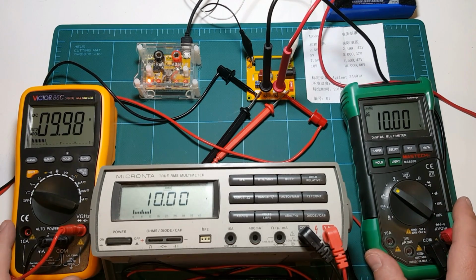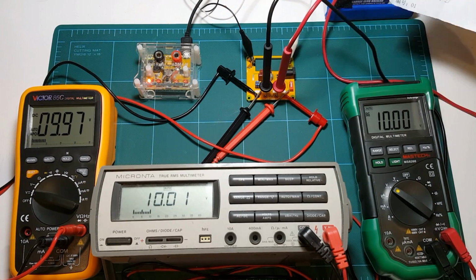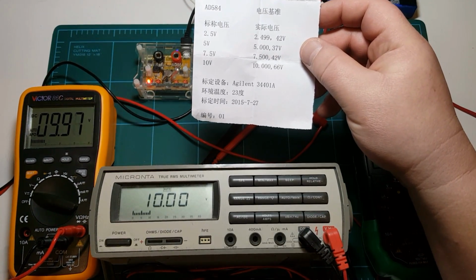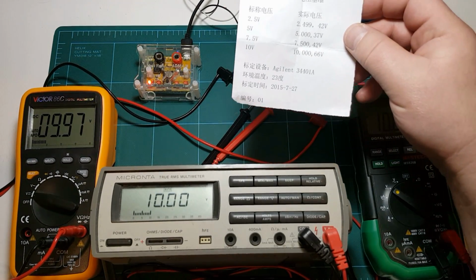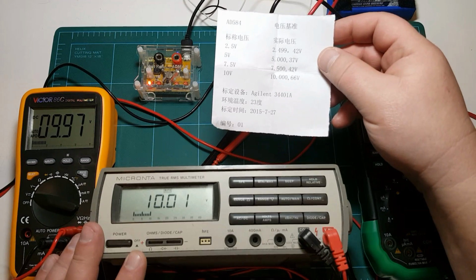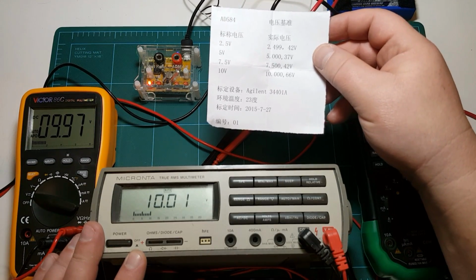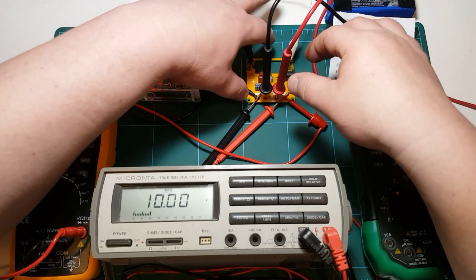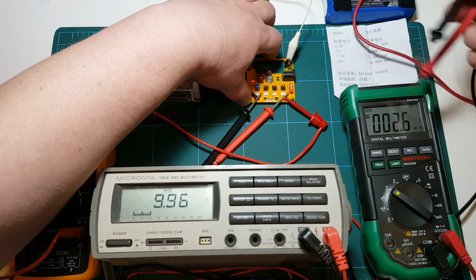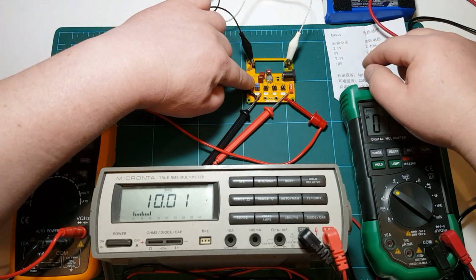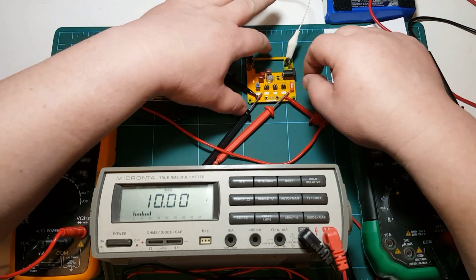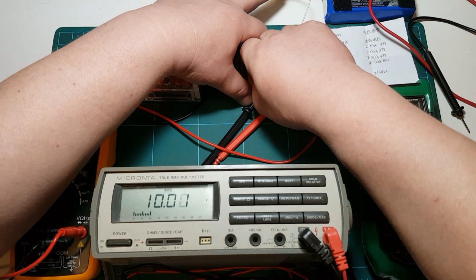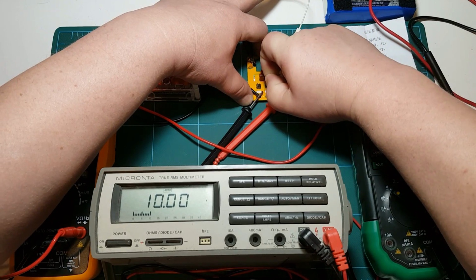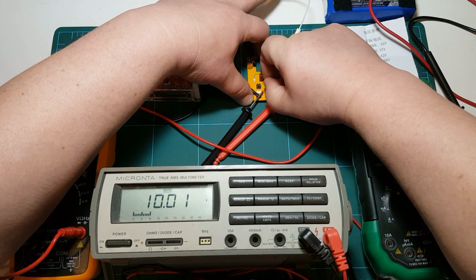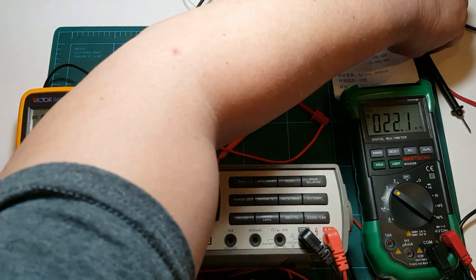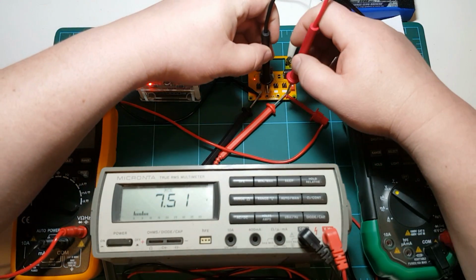So that's the 10 volt range. Let's switch to 7.5 volt. I should be getting 7.50042 volts, which is outside the precision of all these meters, but I'm expecting a reading of 7.500 volts on all three. I'm going to unplug these two probes because they're in my way. To switch voltages, you just move these jumpers from one position to another, which is a little silly — I'd like it better if they used some kind of switch. But that's how this bare bones board operates, one of the cheapest available, so it is what it is.